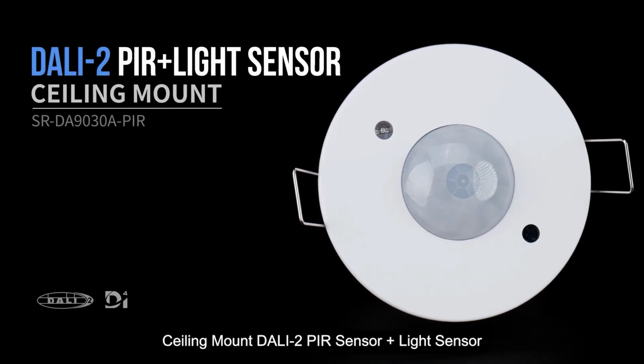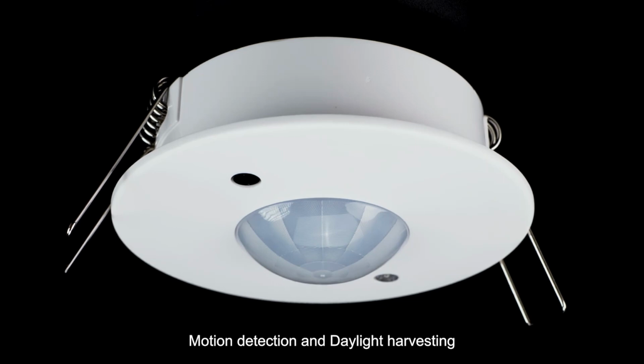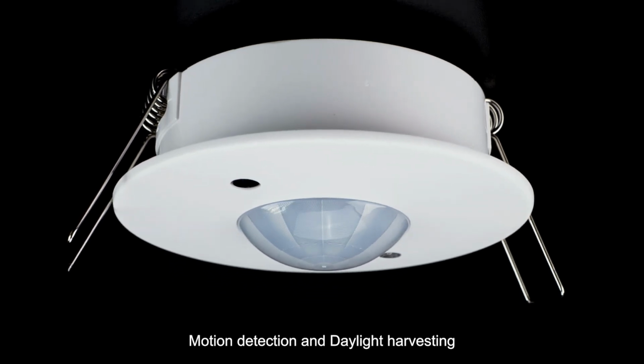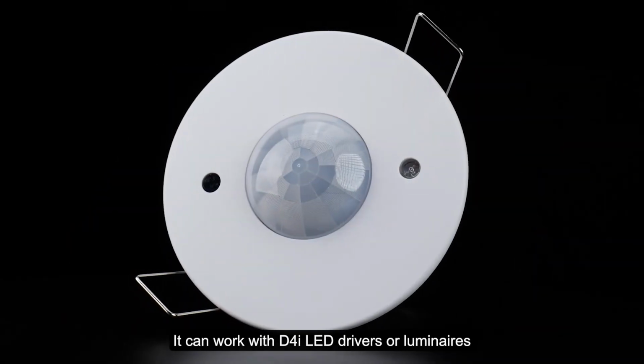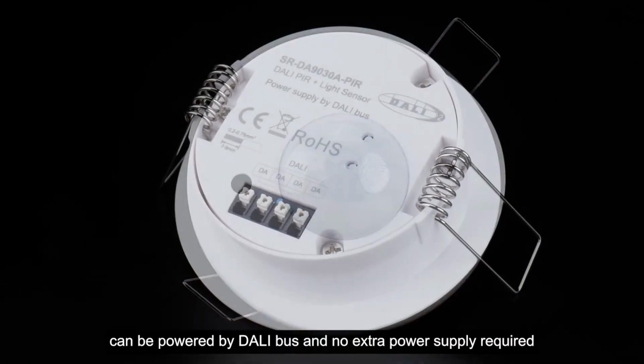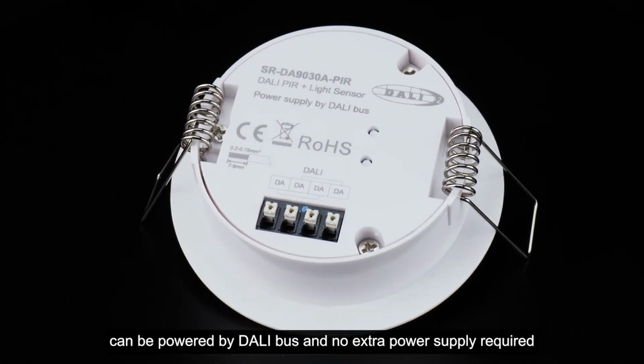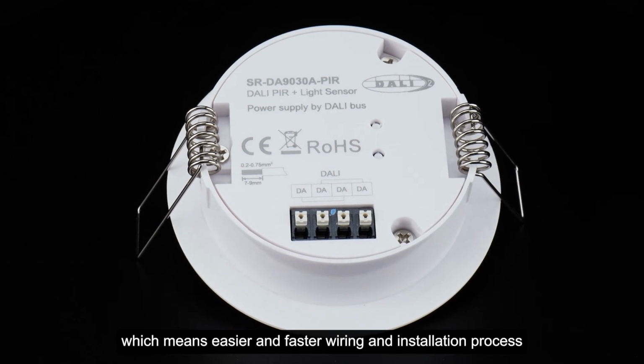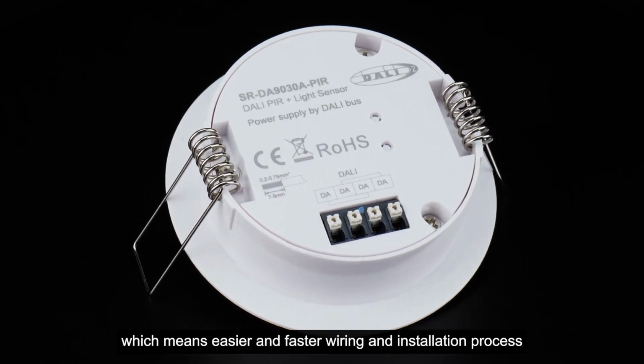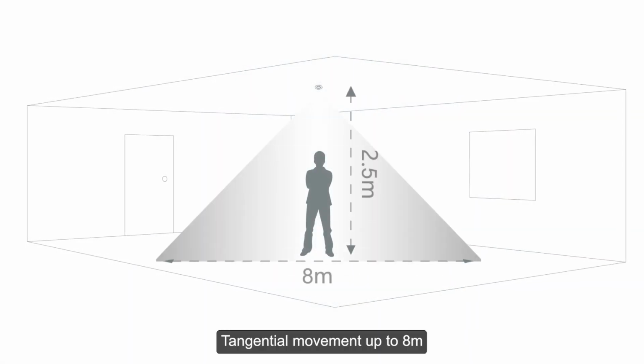Mount DALI-2 PIR sensor plus light sensor. Motion detection and daylight harvesting. It can work with D4i LED drivers or luminaires. Can be powered by DALI bus and no extra power supply required, which means easier and faster wiring and installation process. Tangential movement up to 8 meters.